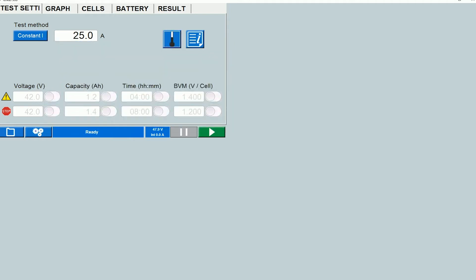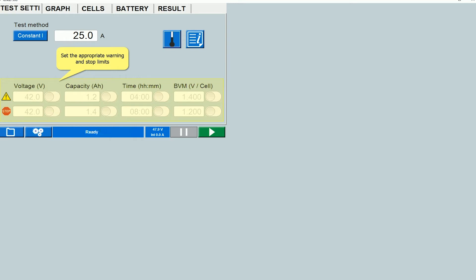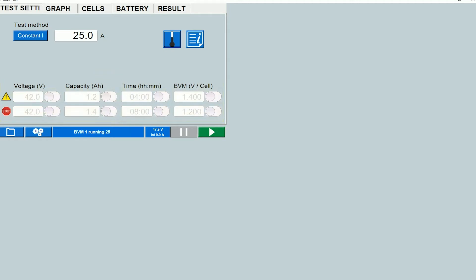Then you will need to enter the warning and the stop limits. Warning limits cause the instrument to put out a warning if the limit is exceeded and stop limits cause the instrument to stop the test if the limits are exceeded. The limits can be set on the basis of four parameters. The overall battery voltage, the capacity, the time and BVM which is the individual cell voltage.